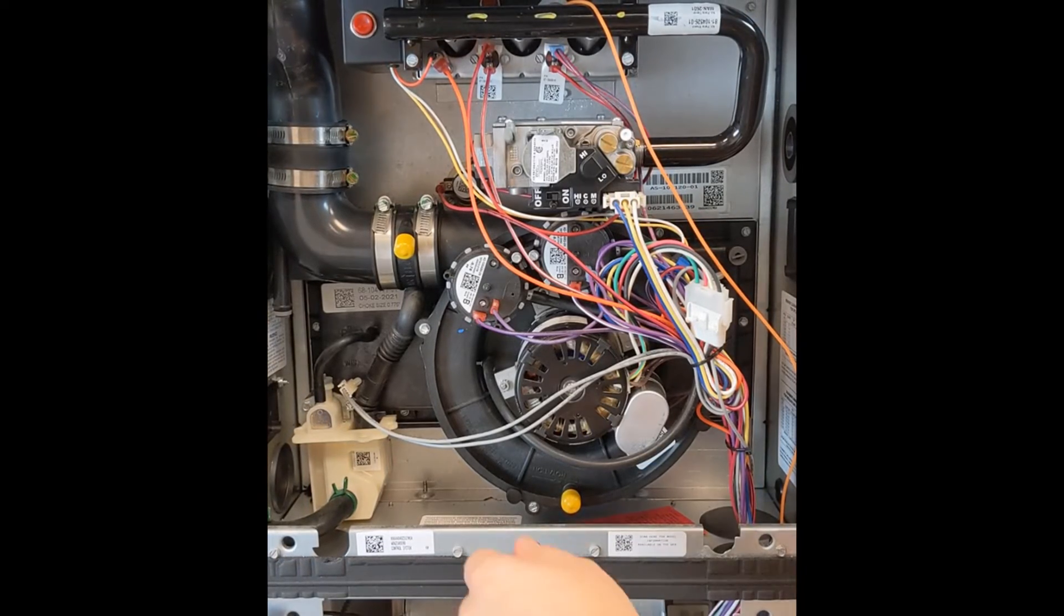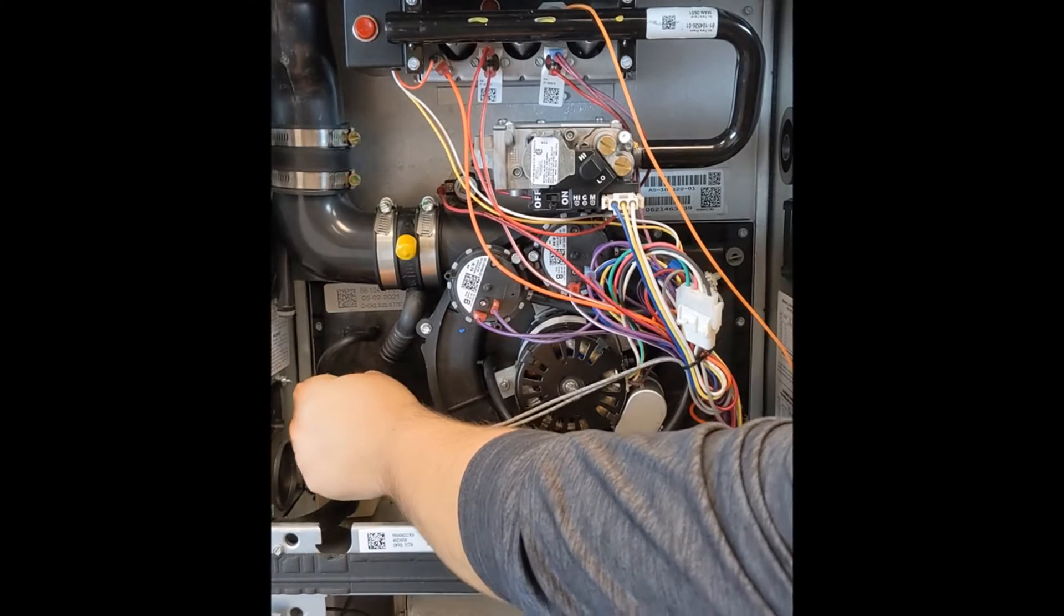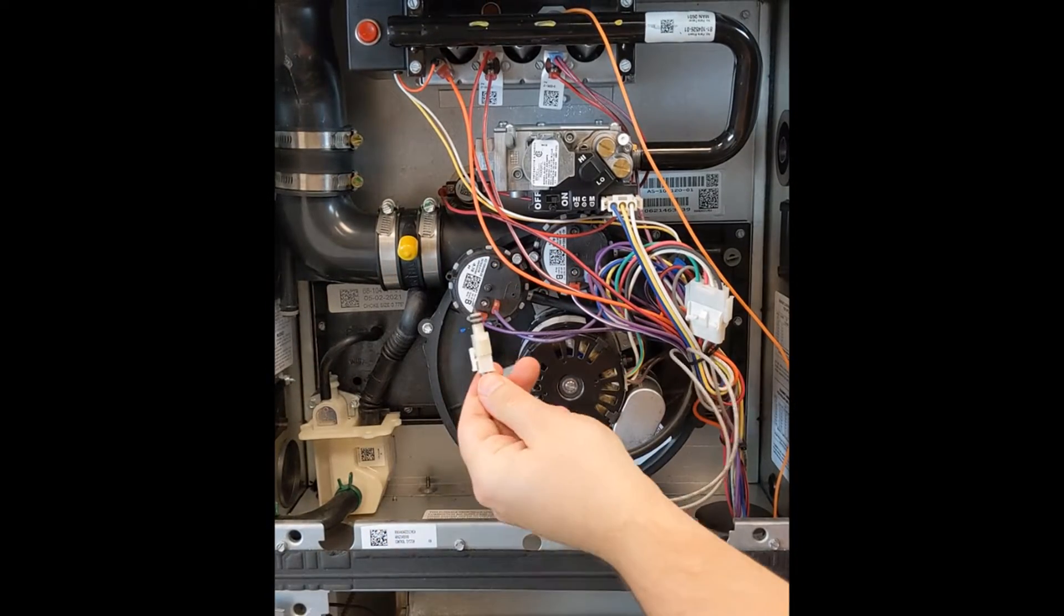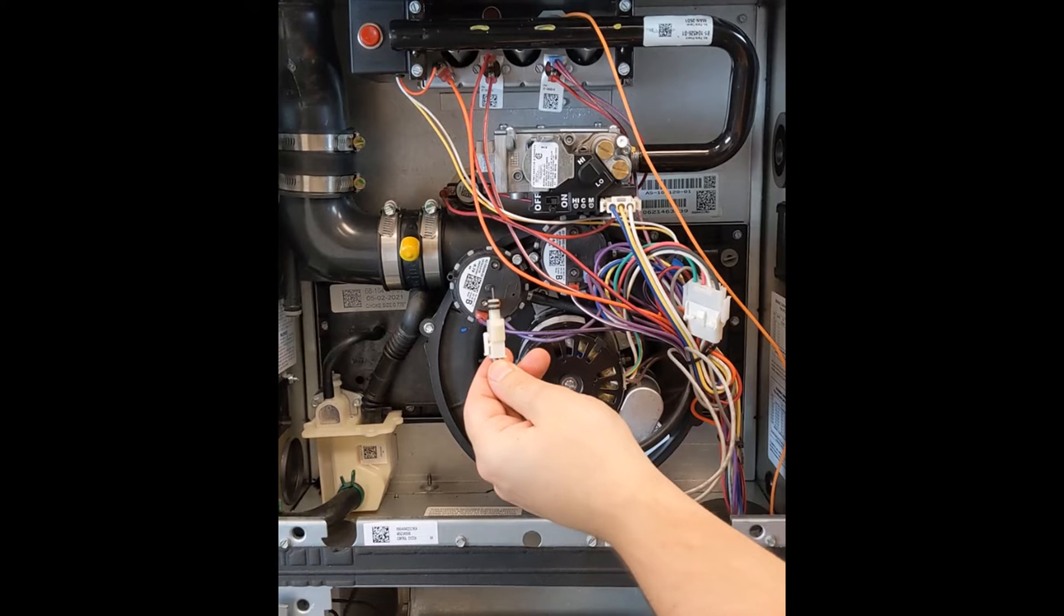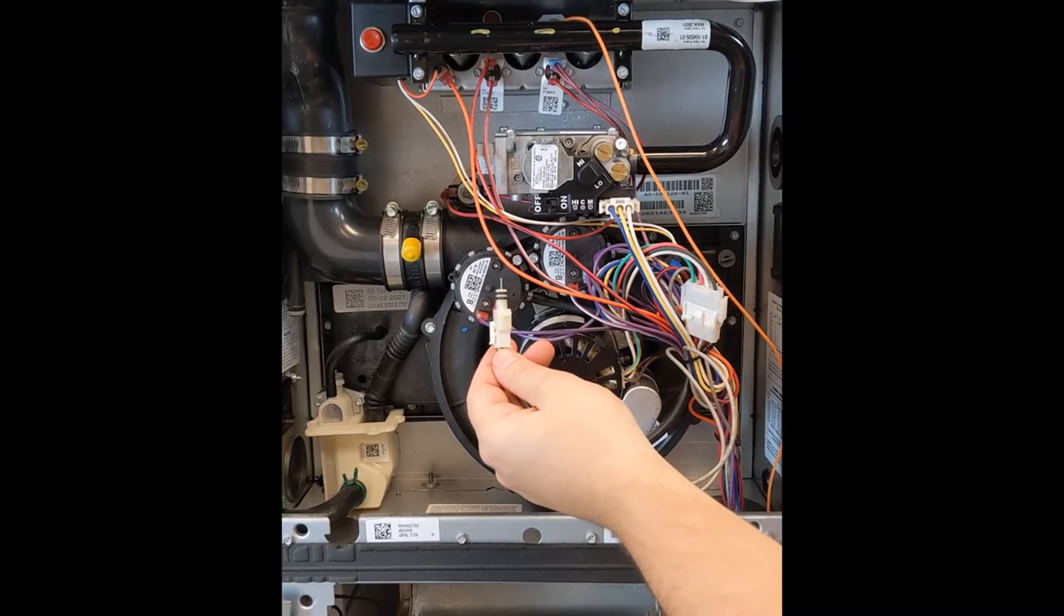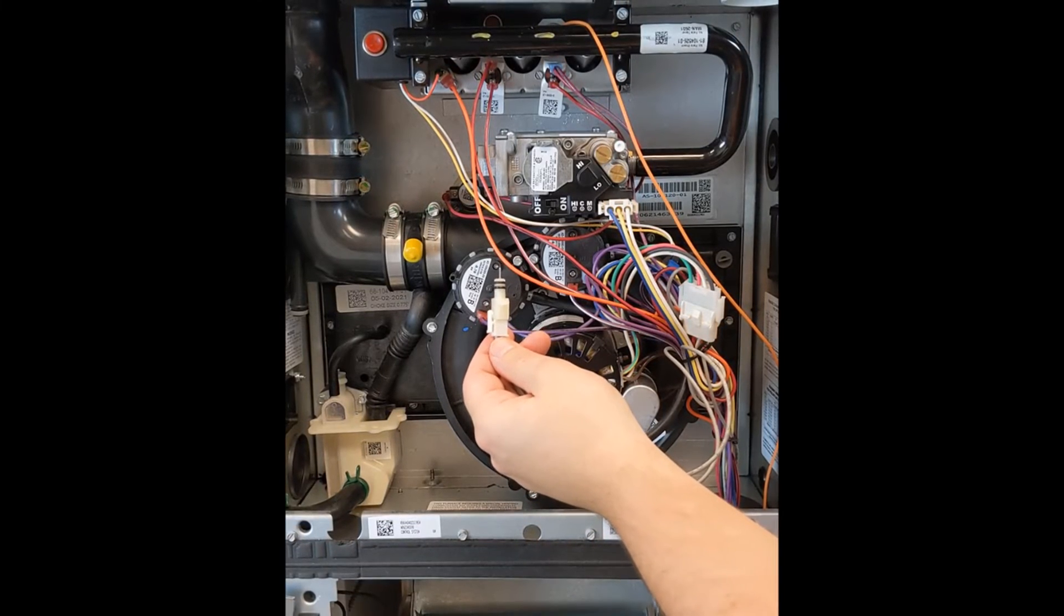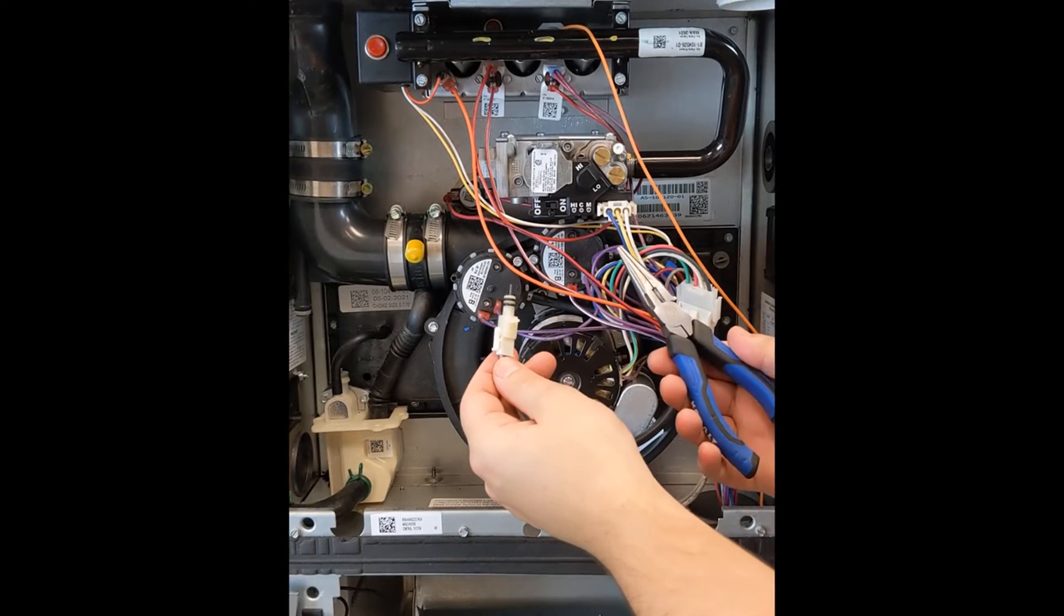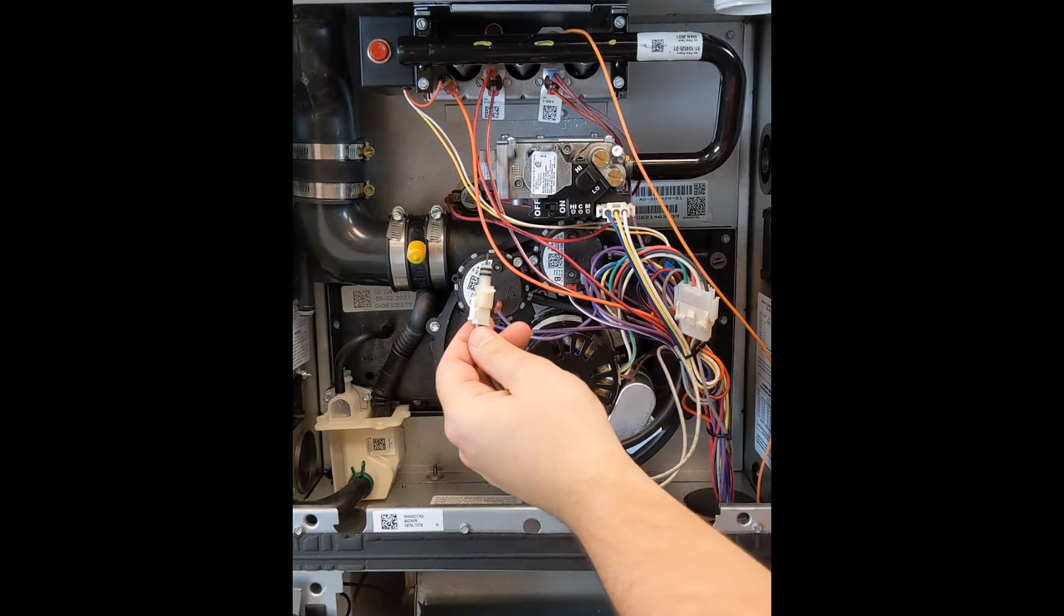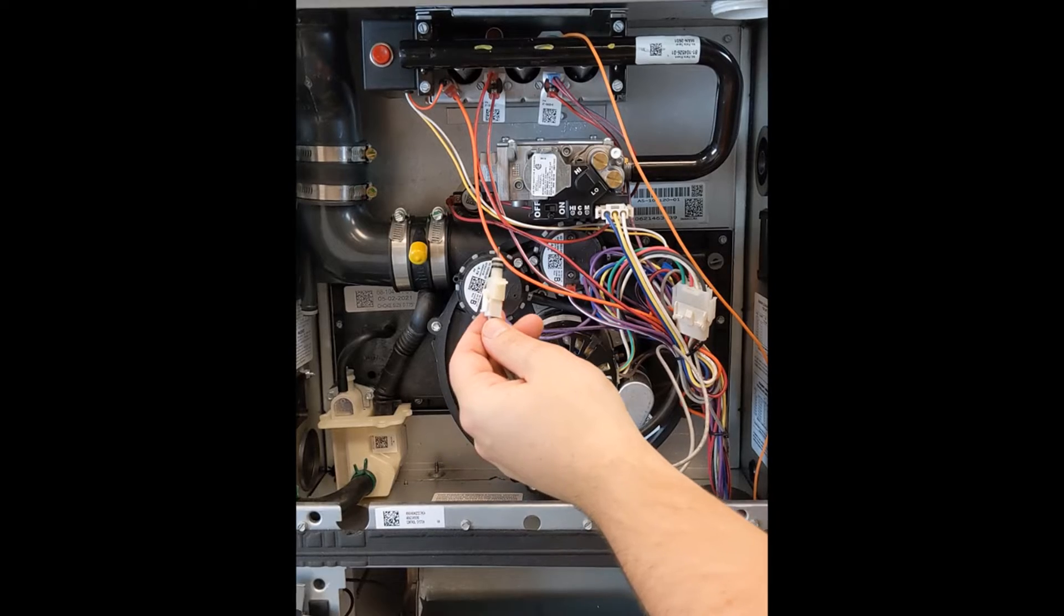Then, one at a time, remove and inspect the water sensors. Please note that these can be very hard to get out, and if you're using pliers, please exercise caution as not to crack the collector box.